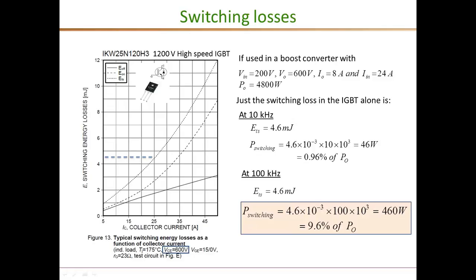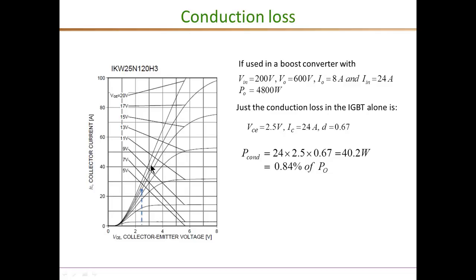Clearly, 460 watts of switching loss is not a practical solution, especially considering there are other losses: conduction loss in the IGBT itself, in the diode, and in the passives. For conduction losses, we look at the figure showing collector-emitter voltage versus collector current. For our specification of 24 amperes, the corresponding VCE is about 2.5 volts. The conduction loss is the forward drop times the current times the duty ratio, which for the 200-to-600-volt step-up is D = 0.67. The conduction loss comes out to be 40.2 watts — roughly less than 1% of total output power — a key advantage of the IGBT.